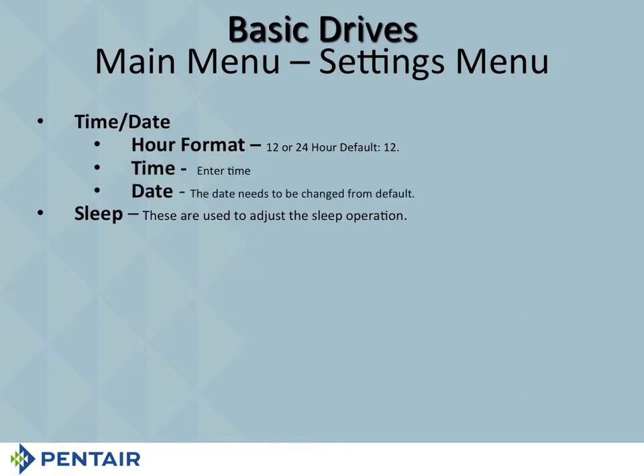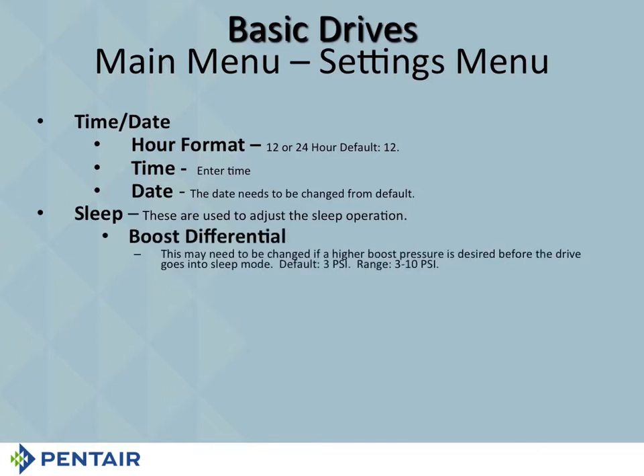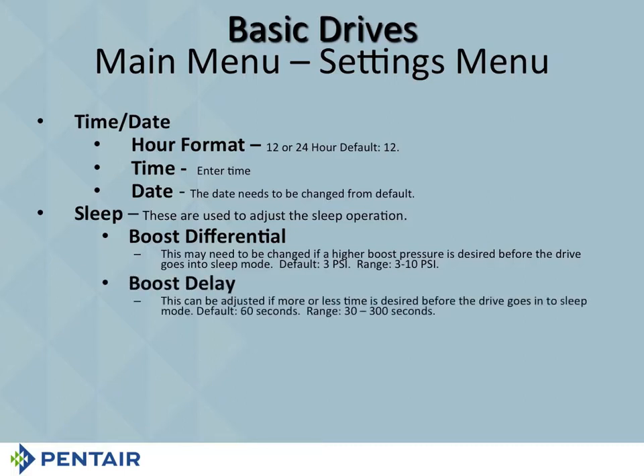Under sleep, if you don't do time date, push the down arrow, it'll come up as sleep. If you push the enter button, then it's going to say boost differential. Now remember, we defaulted it to 3, it can go up to 10. The next one down will say boost delay. Again, if you want to change this, hit the enter button. Remember, we say wait 60 seconds and then boost. You can change that all the way down to 30, all the way up to 300 seconds.